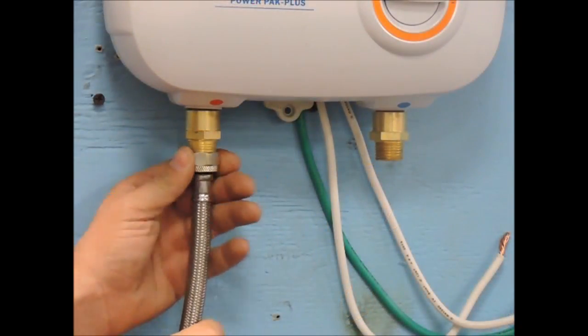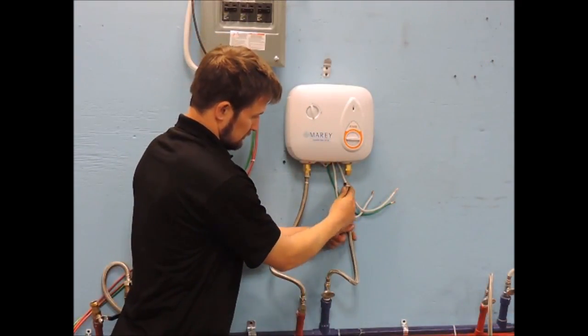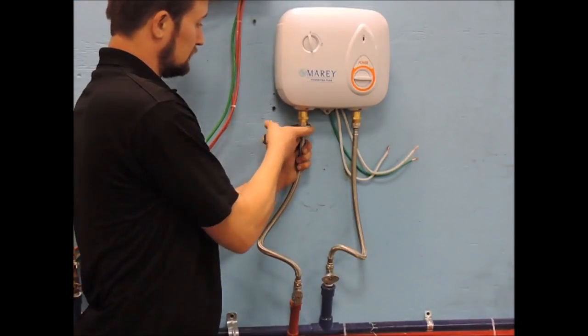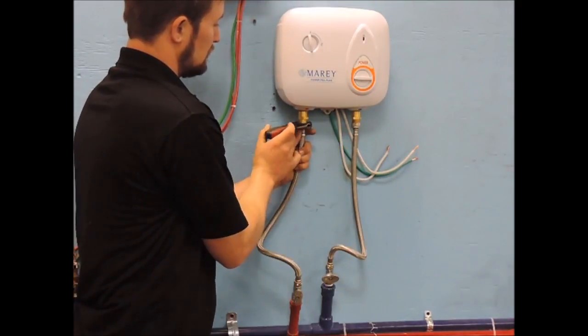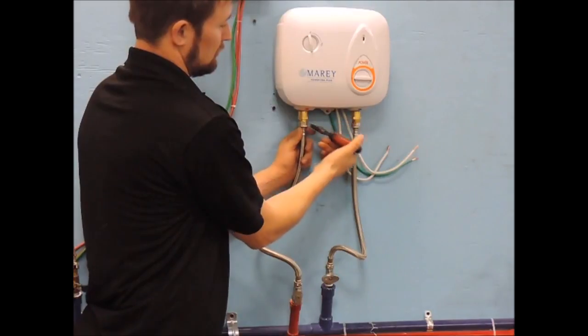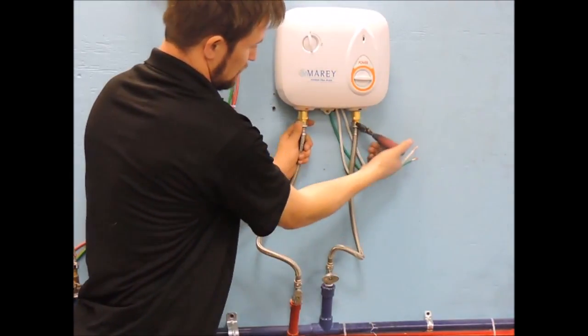The connections are ½ inch NPT for both the inlet and the outlet, and can be found at the bottom of the unit. The cold water inlet is on the right side and should be preceded by a shutoff valve. The hot water outlet is on the left side and runs to your hot water source. Never use PVC on the hot water outlet — use instead CPVC or other heat-rated materials.